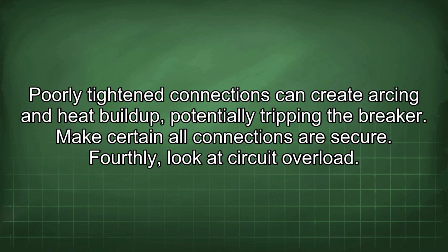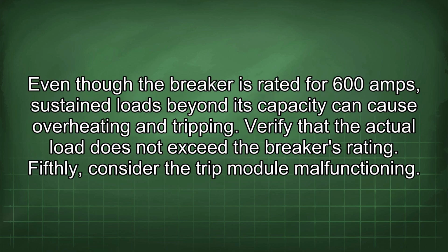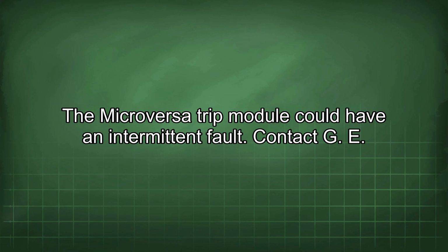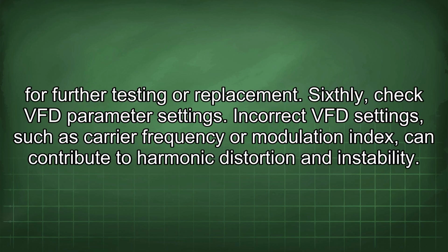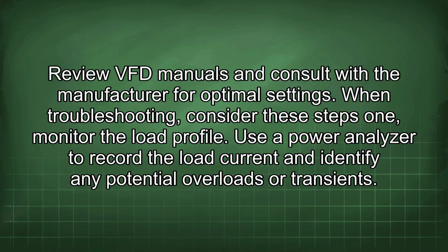Fourthly, look at circuit overload. Even though the breaker is rated for 600 amps, sustained loads beyond its capacity can cause overheating and tripping. Verify that the actual load does not exceed the breaker's rating. Fifthly, consider the trip module malfunctioning. The Microversa trip module could have an intermittent fault. Contact GE for further testing or replacement. Sixthly, check VFD parameter settings. Incorrect VFD settings, such as carrier frequency or modulation index, can contribute to harmonic distortion and instability. Review VFD manuals and consult with the manufacturer for optimal settings.